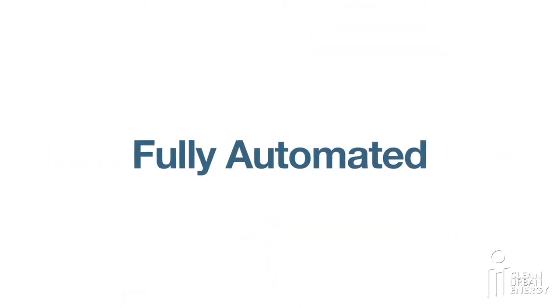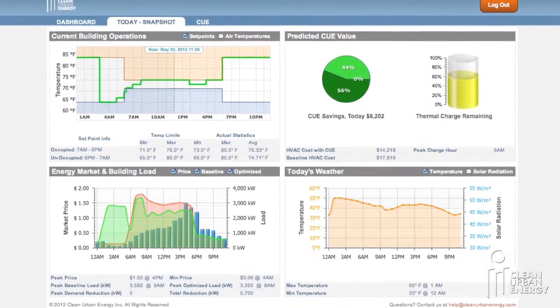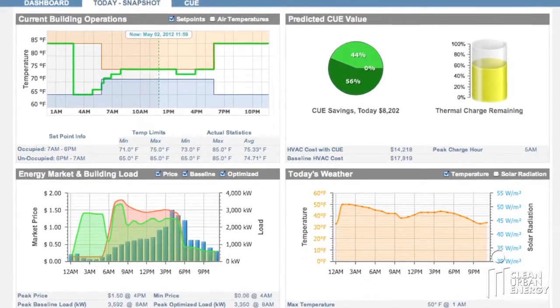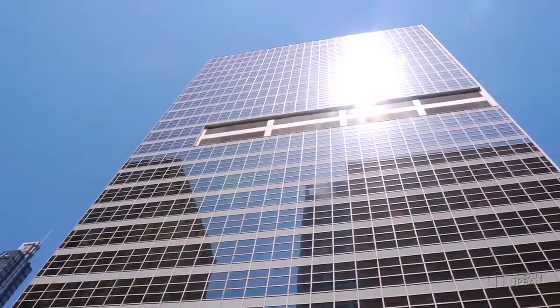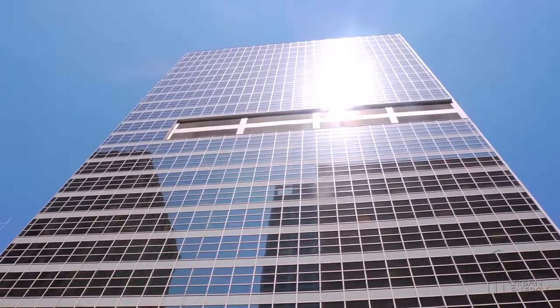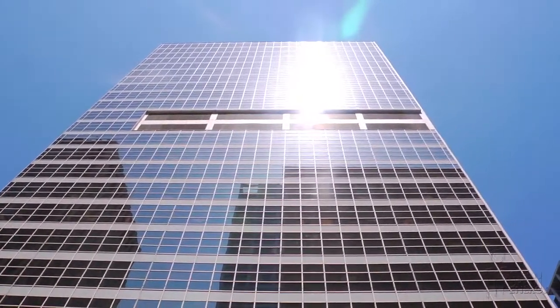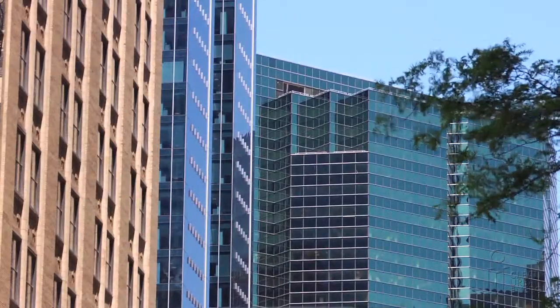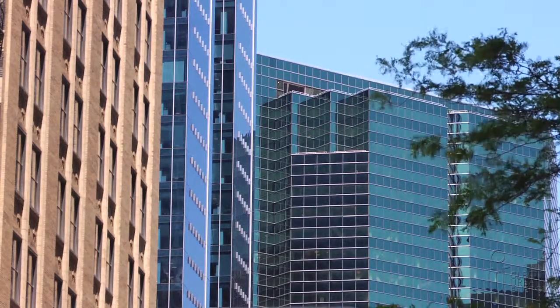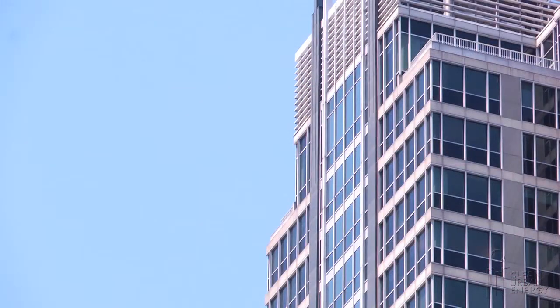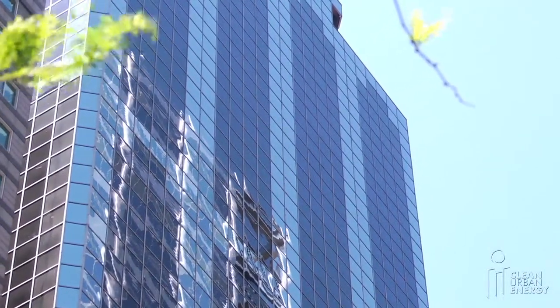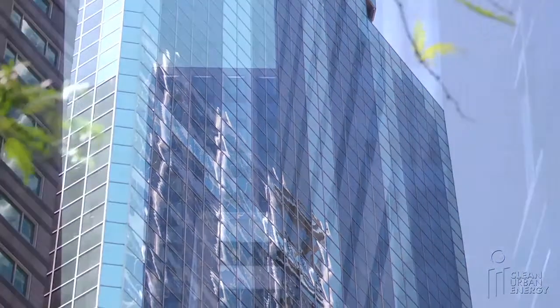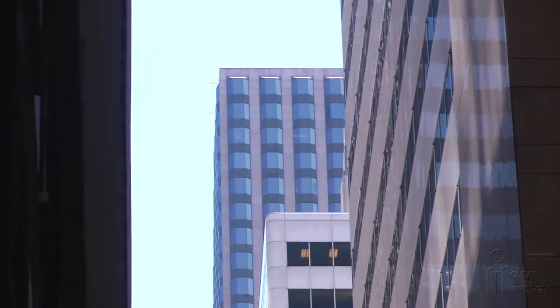The best part is that the system is fully automated. Once a building is in production, we source weather data and leverage our building model to predict hourly cooling requirements. Our cloud application then integrates day-ahead electricity prices and utility tariff rates to identify the optimal set point strategy, and automatically implements it to operate the building at the lowest cost without adversely affecting tenant comfort. Our solution is unique in that it predicts versus responds, and implements versus notifies, virtually eliminating the need for manual intervention by the facility operations team.